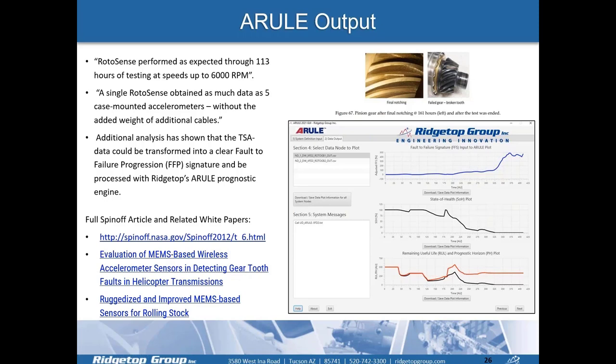As a result of the NASA testing, RotoSense performed as expected through 113 hours of testing at speeds of up to 6,000 RPM. A single RotoSense unit obtained as much data as five case-mounted accelerometers without the added weight of additional cables. Additional analysis showed that the time synchronous averaging data could be transformed into a clear fault-to-failure progression signature and processed with Ridgetop's A-RULE prognostic engine. Additional details are available in published papers.